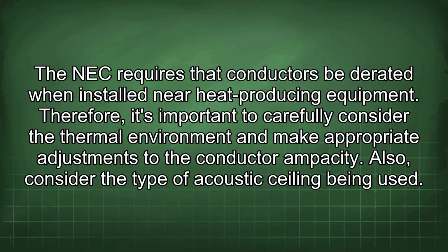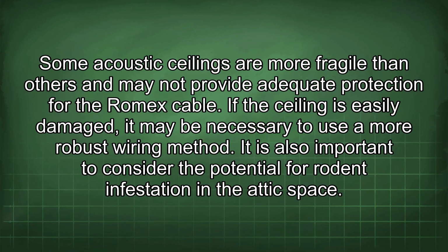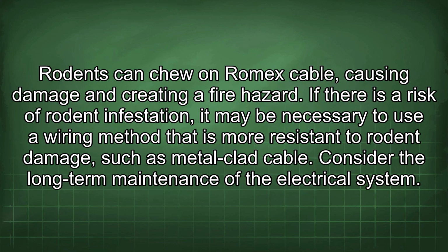Also, consider the type of acoustic ceiling being used. Some acoustic ceilings are more fragile than others and may not provide adequate protection for the Romex cable. If the ceiling is easily damaged, it may be necessary to use a more robust wiring method. It is also important to consider the potential for rodent infestation in the attic space. Rodents can chew on Romex cable, causing damage and creating a fire hazard.